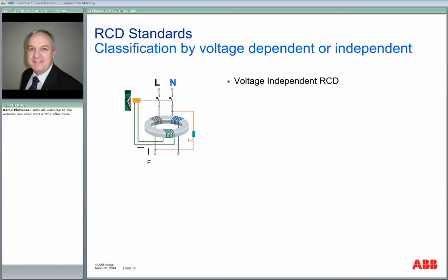So following on to that question, is it reliable enough to connect to the output of a UPS? I think the reliability of the RCD or the RCBO is not really in question. Certainly they can exist on the output side or the load side of a UPS without any problems at all. So it really depends on the load that they're connected to and the types of influences coming back. We'll have a chat about the loads a little bit later because there's some pretty important information that I can actually share with you on that.